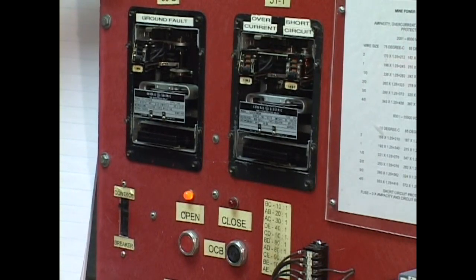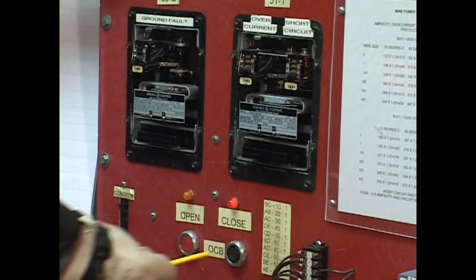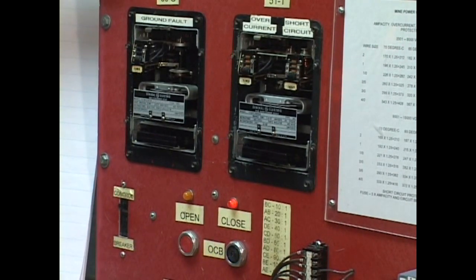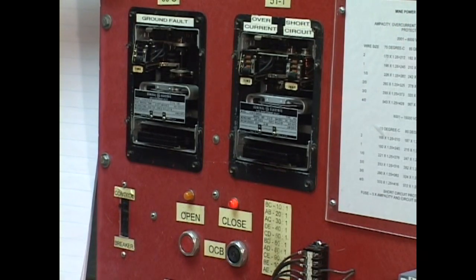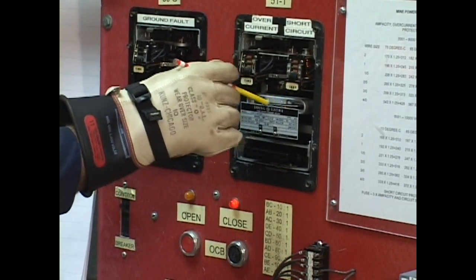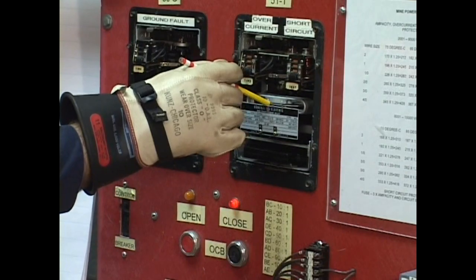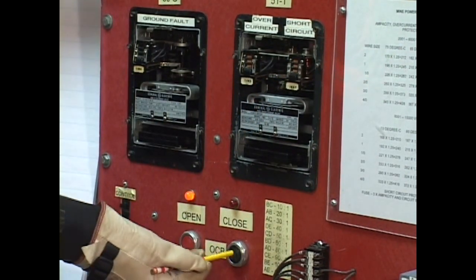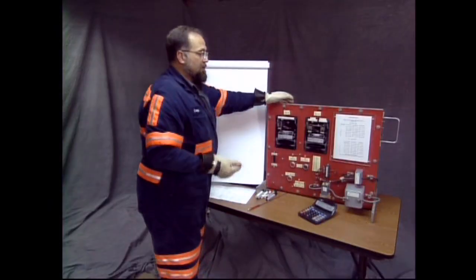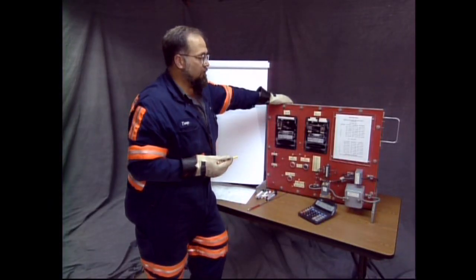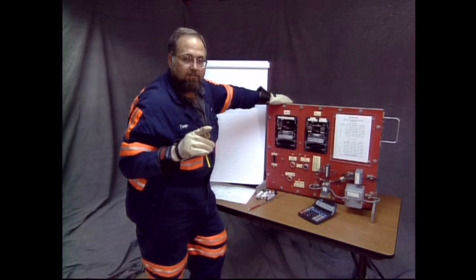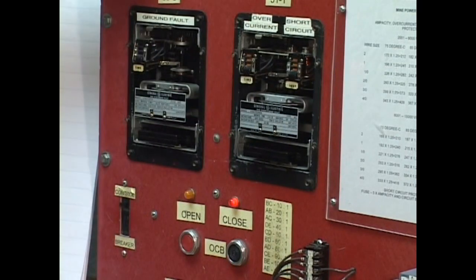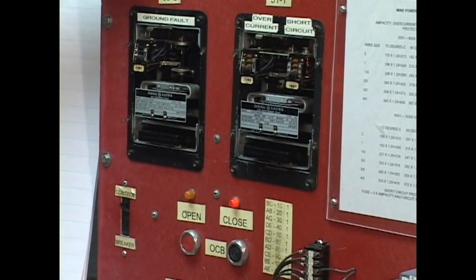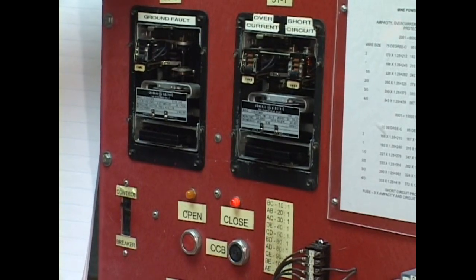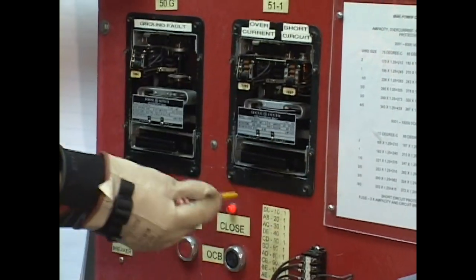Opens the breaker. The breaker opened. I'm going to reclose my OCB. I'm going to manually operate my overcurrent time disc. Here we go. We're going to turn the disc around, make contact on that post, and the breaker opened. That completes the manual operation of one auxiliary device. This device is one device. It has 3 functions that you need to test, but the device, this is 51.1.